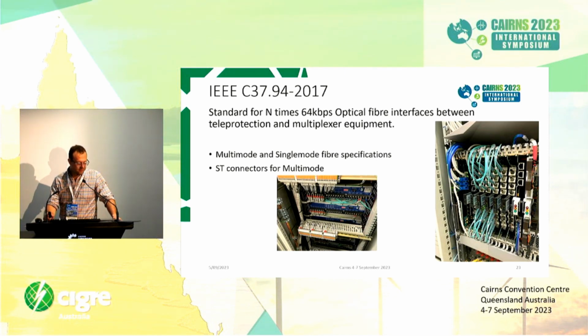The protocol, as it says up there, defines a number of 64 kilobit per second optical interfaces, up to a maximum of 12. In our experience, N, as the number of channels here, is most nominally set to 1. One of the positives of C37.94 is that it's supported via an RFC for conversion to packet, and some of the eagle-eyed amongst you may notice the missing dust caps that have been reinstalled.